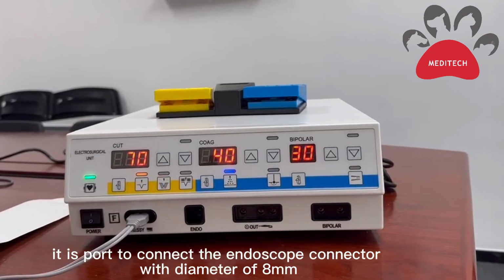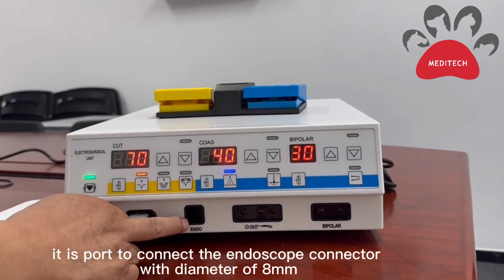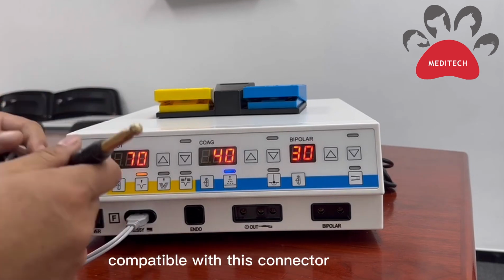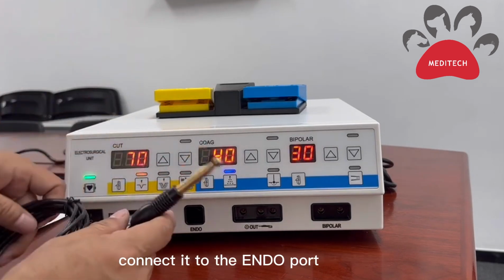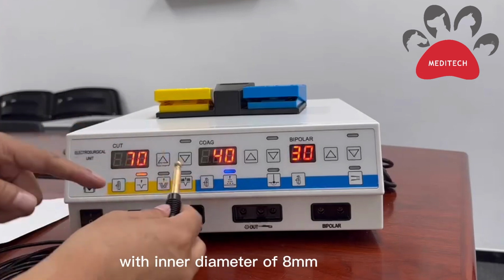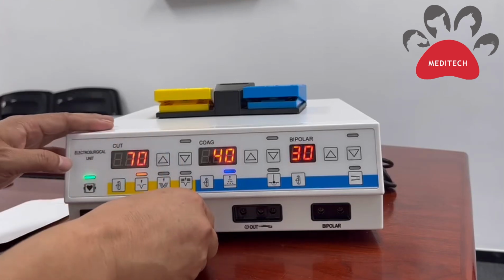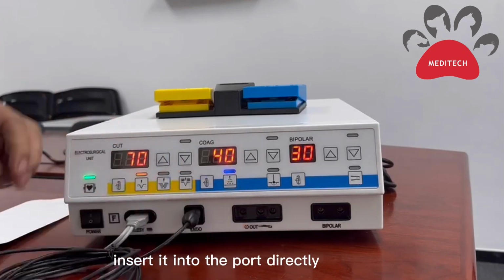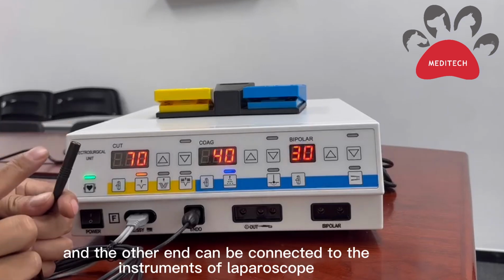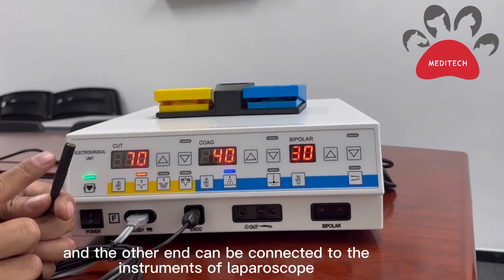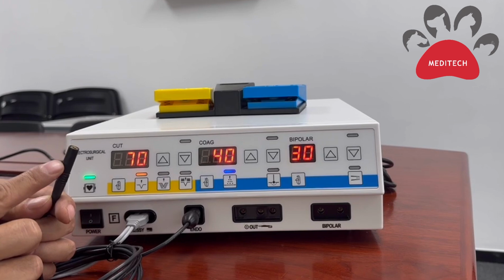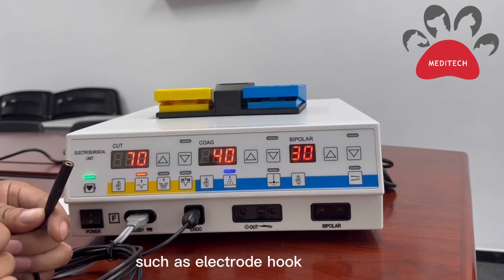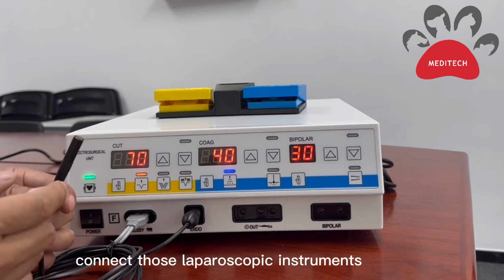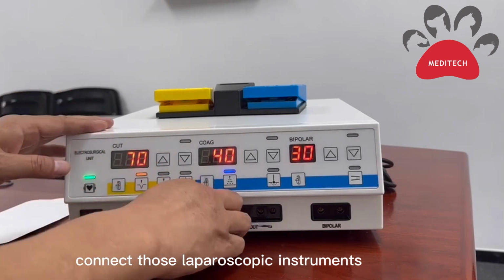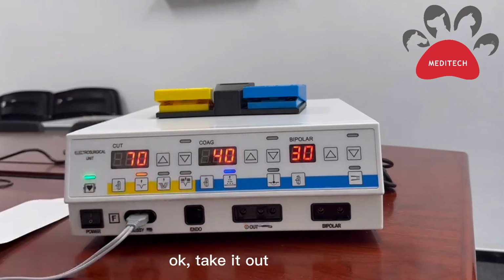This is the port to connect the endoscope connector with diameter of 8 mm. Compatible with this connector, connected to the endo port. With inner diameter of 8 mm, it is inserted into the port directly. And the other end can be connected to the instruments of laparoscope, such as electrode hook, electrode ballpoint. Connect those laparoscopic instruments. OK, take it out.